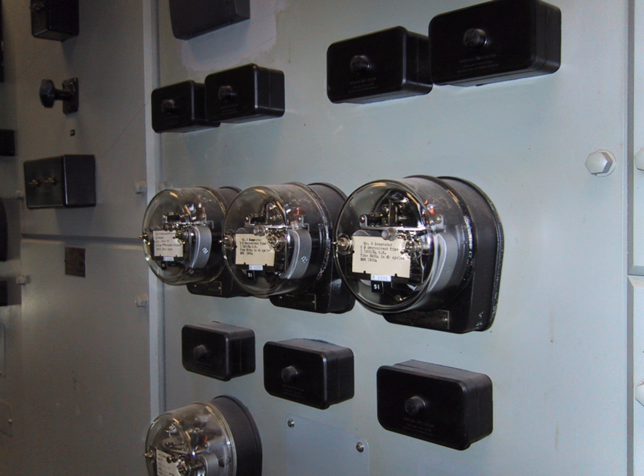Topic: Instantaneous overcurrent relay. An instantaneous overcurrent relay is an overcurrent relay which has no intentional time delay for operation. The contacts of the relay are closed instantly when the current inside the relay rises beyond the operational value. The time interval between the instant pickup value and the closing contacts of the relay is very low. It has low operating time and starts operating instantly when the value of current is more than the relay setting. This relay operates only when the impedance between the source and the relay is less than that provided in the section.